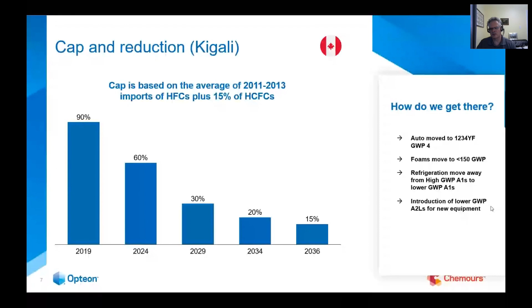The first thing is the cap and reduction. The GWP of refrigerants is multiplied by how many kilograms are imported, and they come up with a cap, and then there's a reduction. We're already at the 60% reduction, and it's been quite successful thus far. A big part of it has been automotive, a move to a low GWP refrigerant called 1234YF. Foams have moved to low GWP solutions as well, which was very painful in that industry, but they too have moved. In our sector, we've also seen refrigerants move to lower GWP, non-flammable A1 refrigerants like 448, 449, etc. But as time marches on, we need to start introducing even lower GWP solutions, many of which will fall into this A2L category.